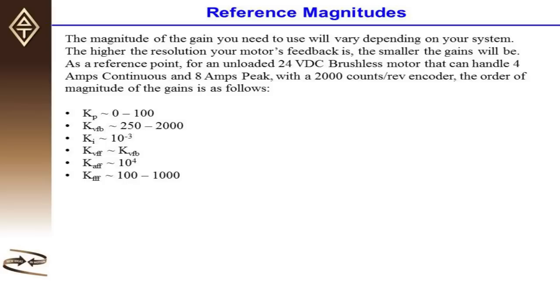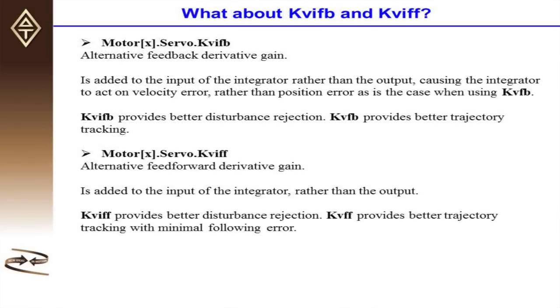KVFB is roughly between 250 and 2000. KI is on the order of 10 to the negative 3. KVFF is almost always the same magnitude as KVFB. KAFF is on the order of 10,000. KFFF is usually between 100 and 1000 for this particular kind of motor, just as a reference point for you.